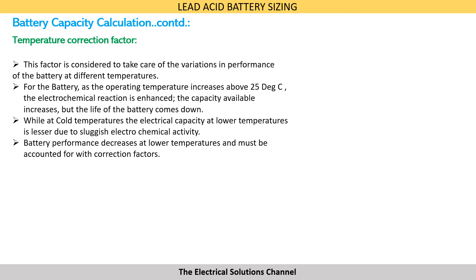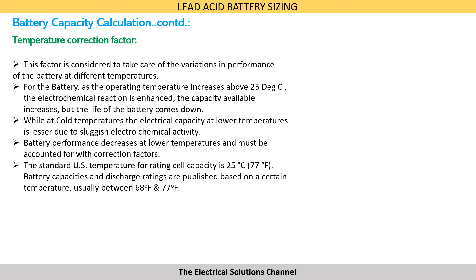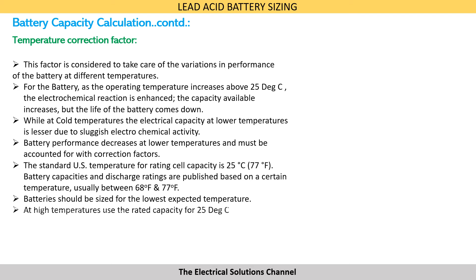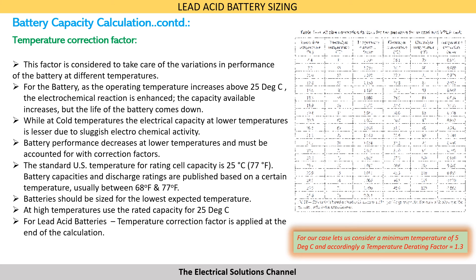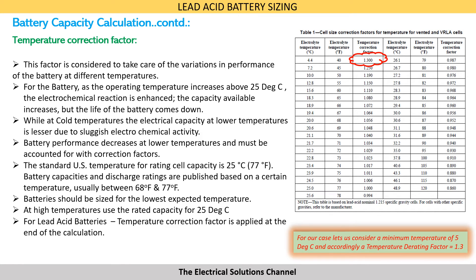The standard US temperature for rating cell capacity is 25°C or 77°F. Battery capacities and discharge ratings are published by battery vendors based on a certain temperature, usually between 68°F to 77°F. Batteries should be sized for the lowest expected temperature; at higher temperatures, use the rated capacity for 25°C. For lead acid batteries, the temperature correction factor is applied at the end of the calculations. For our case, let us consider a minimum temperature of 5°C, and accordingly a temperature correction factor of 1.3 is selected.